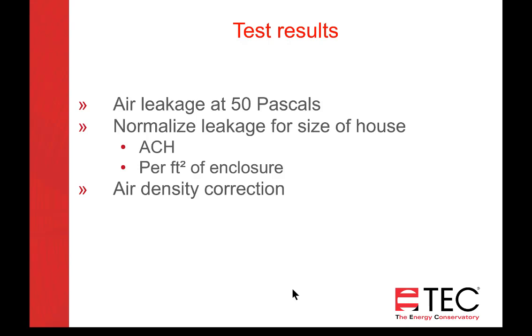The air density correction becomes important, especially if you're in a climate like ours, where we have extreme conditions and we can get below zero. You can have more than a 10% density correction. So it becomes important, especially for code compliance, to include that. Temperature difference and elevation are the two things considered in that air density correction, and the software and apps do that, so that's helpful.